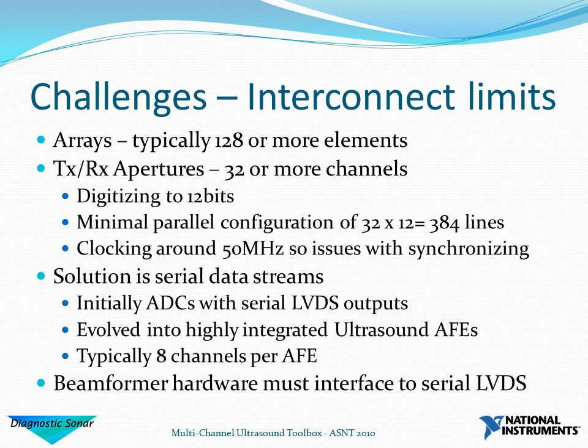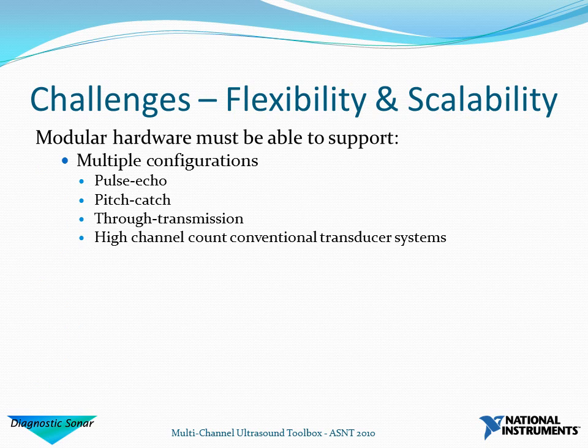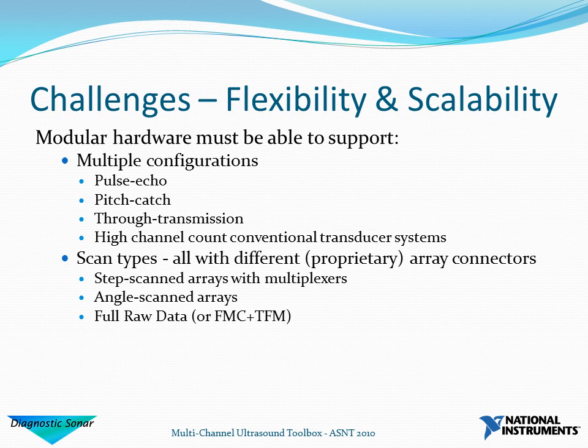Whatever implementation we use, our beamformer hardware is going to have to be capable of interfacing to serial LVDS. We also need to address requirements for flexibility and scalability. We want modular hardware that can support all different standard configurations: Pulse Echo, where transmit and receive are the same; Pitch Catch, where you may have separate transmitter and receiver arrays on the same side; and Through Transmission, where transmit and receive arrays are on opposite sides. We also need to address requirements from conventional transducer systems with multiple and high channel counts, and a variety of different scan types with different and often proprietary array connectors.